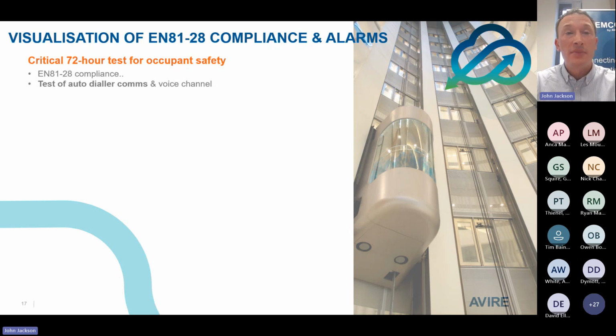So typically in most auto dialers, you would have this as a standard setting. There are building owners who like a tighter time threshold on this test, and we see some national infrastructure companies doing this every 24 hours, for example. So this is something that can be changed within the auto dialer itself. The test itself would check the overall call via DTMF tones, and it also opens up the voice channel to enable and check that it's working.